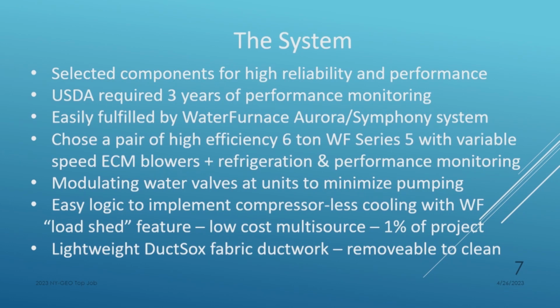And I can tell you, this job is an hour from me. It saved me a lot of trips out to the site because I could tweak stuff from my home. It was a good thing. We've collected a ton of data. Otherwise, we would have to put a pretty sophisticated data collection system in. We also used modulating water valves to minimize pumping everywhere we could. Again, with the AXB board in the WaterFurnace, it's easy to do with the load shed. Basically it shuts the compressor off, and it runs just the blower. So it's easy to implement this waterside economizer.